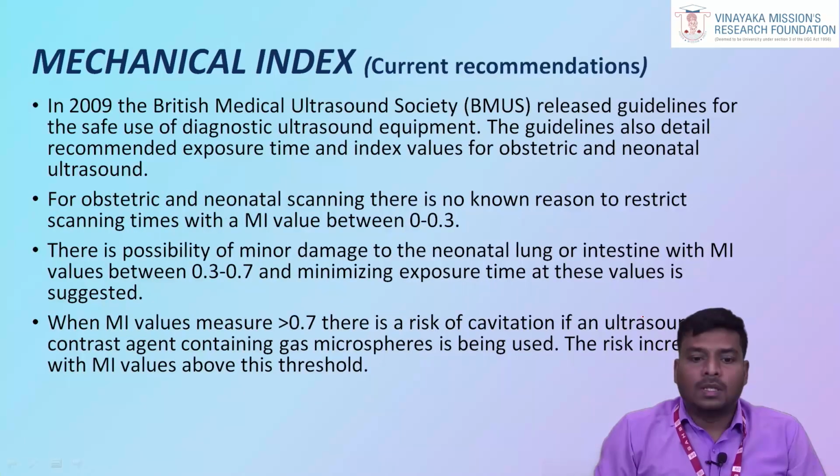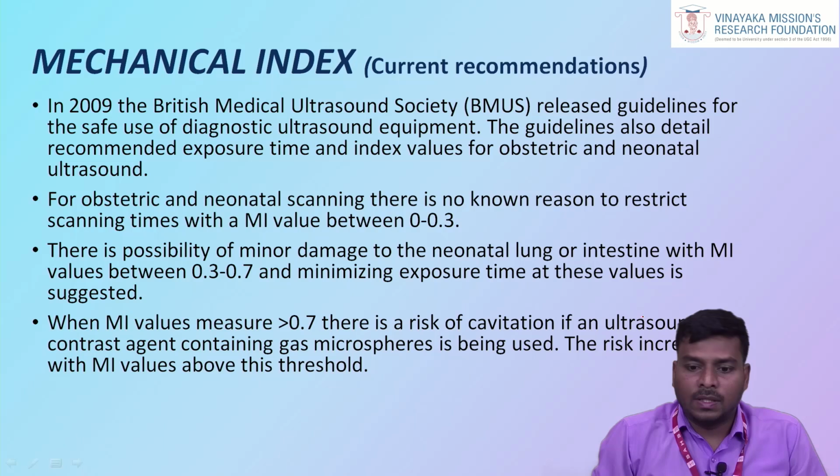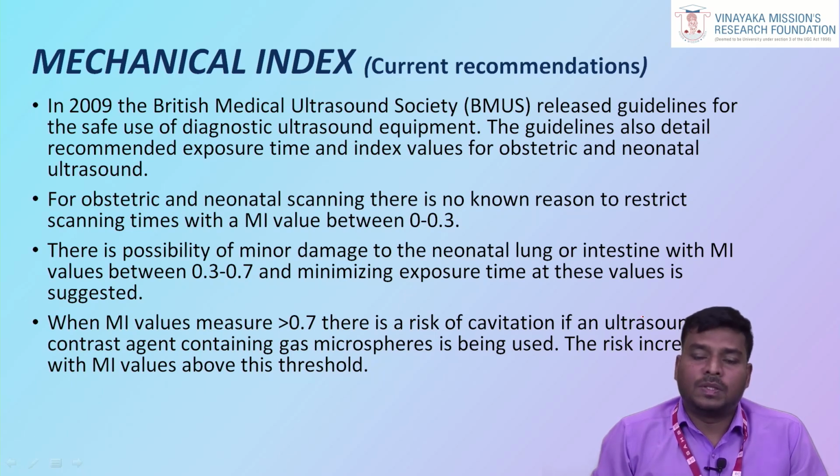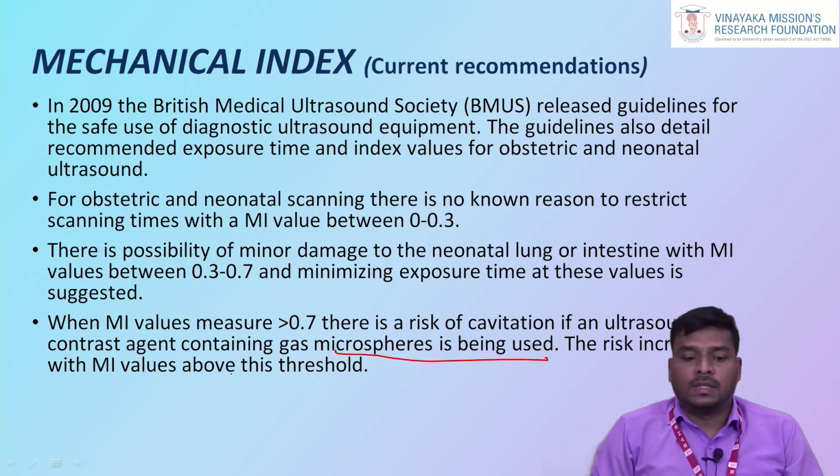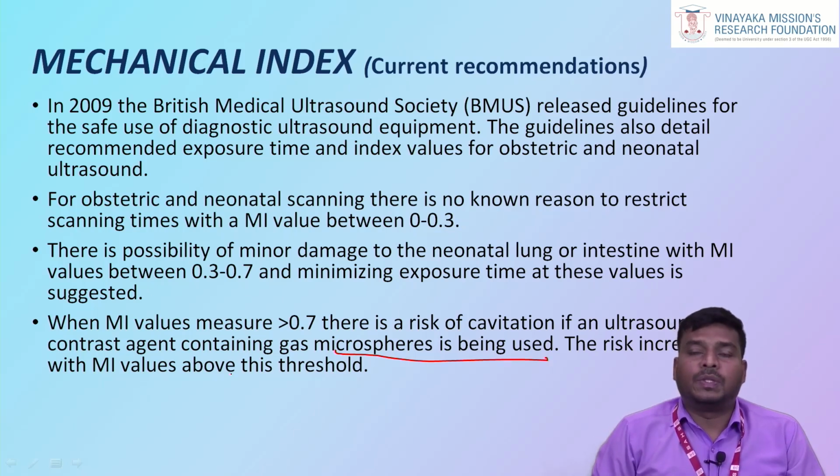We discussed the British Medical Ultrasound Society. For obstetric and neonatal scanning, there is no known reason to restrict scanning time with an MI value below 0.3. When the MI value is above 0.7, there is a risk of cavitation if an ultrasound contrast agent containing gas microspheres is being used. The risk increases with MI values above the threshold.